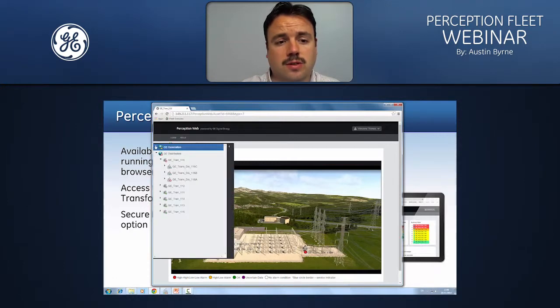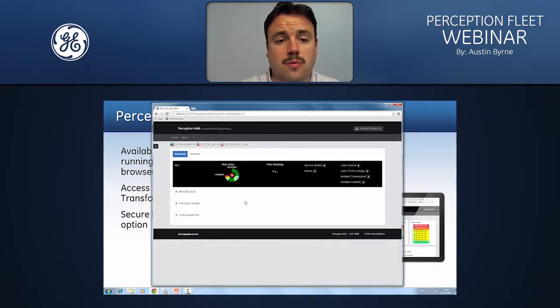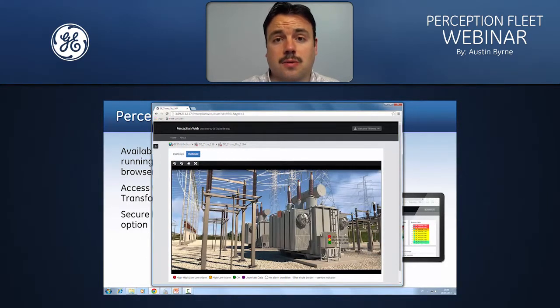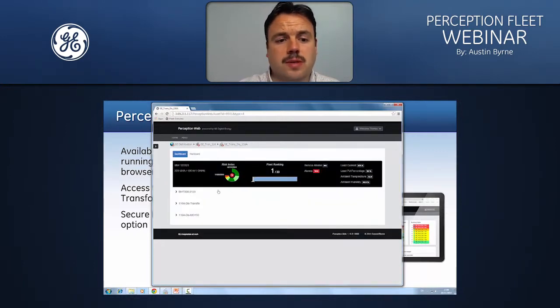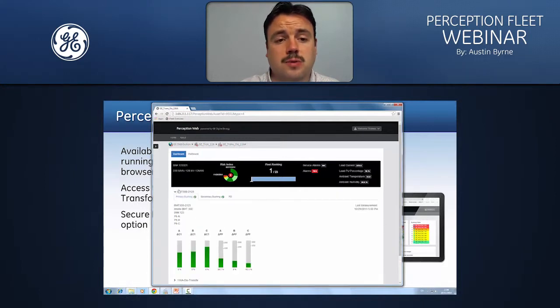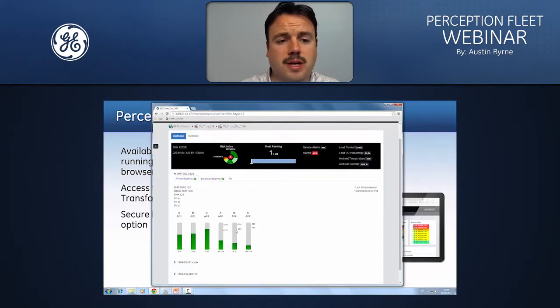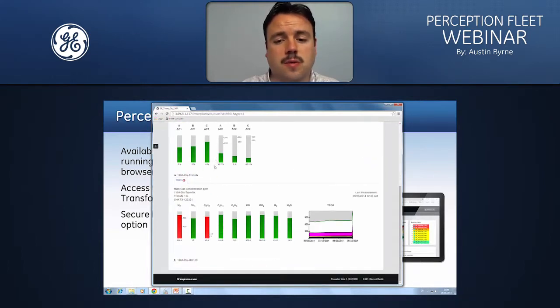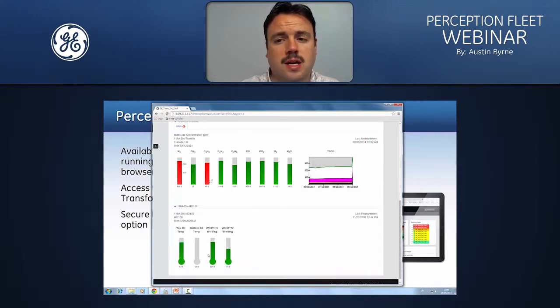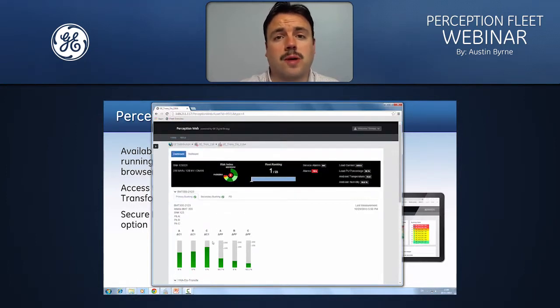So again, I can drop down to that particular transformer and I can see another wallboard showing exactly what's happening within that asset and where the alarms are coming from. So the alarm is coming from my multi-gas product, as you can see here. As per the Perception desktop application, I also have the fleet dashboard showing the most critical data. So you can see we have our bushing information, we have our dissolved gas concentration taken from our multi-gas product, and then we have our MO150 information, and this is all accessible through any modern web browser.